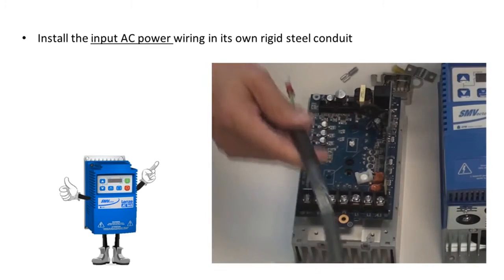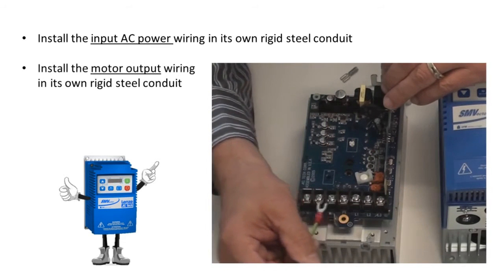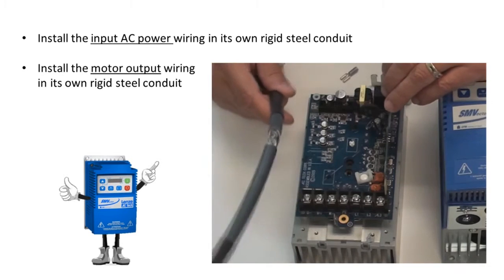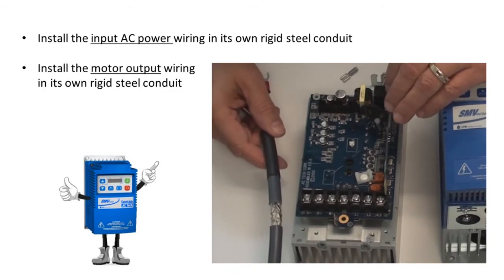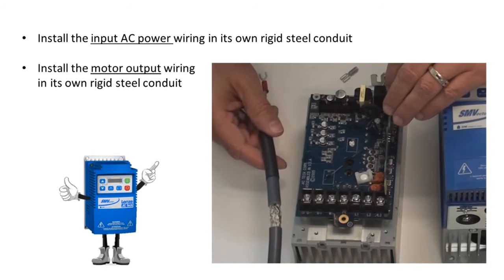So by connecting the motor power wires to these screws, they would go in their own separate conduit. And likewise, our input power wiring would go in its own rigid steel conduit.